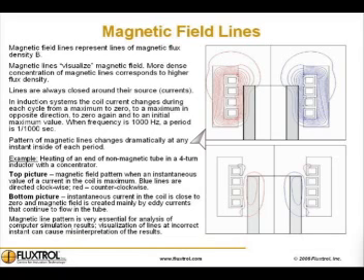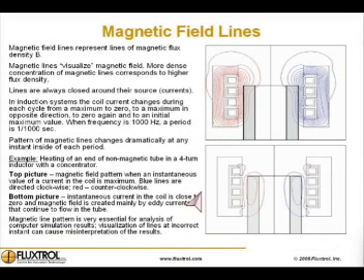For example, consider the heating of the end of a non-magnetic tube in a four-turn inductor with a concentrator. Here we see a magnetic field pattern when the instantaneous value of current in the coil is maximum — blue lines are directed clockwise and red lines counterclockwise. Here, instantaneous current in the coil is close to zero, and the magnetic field is created mainly by eddy currents.